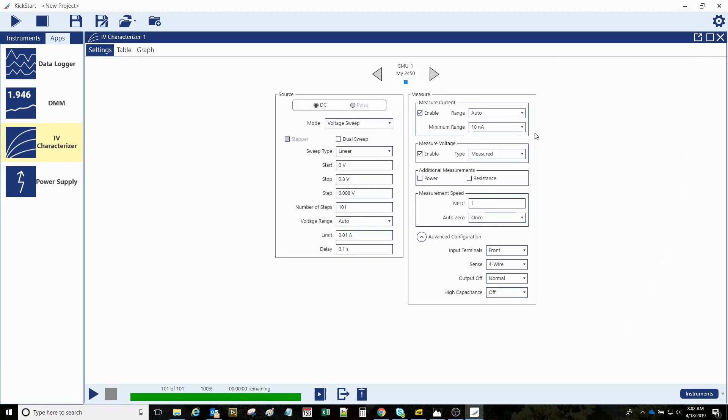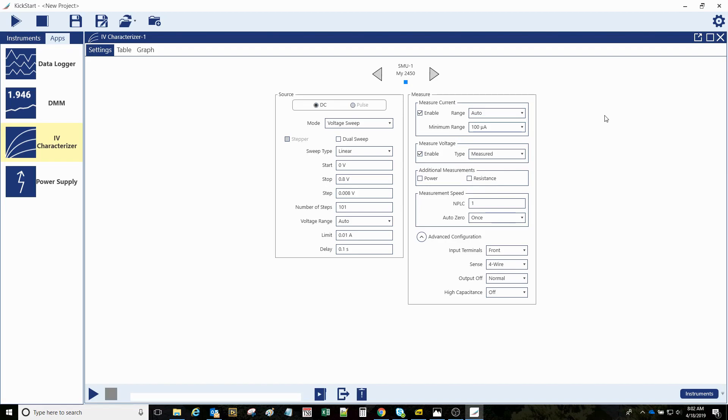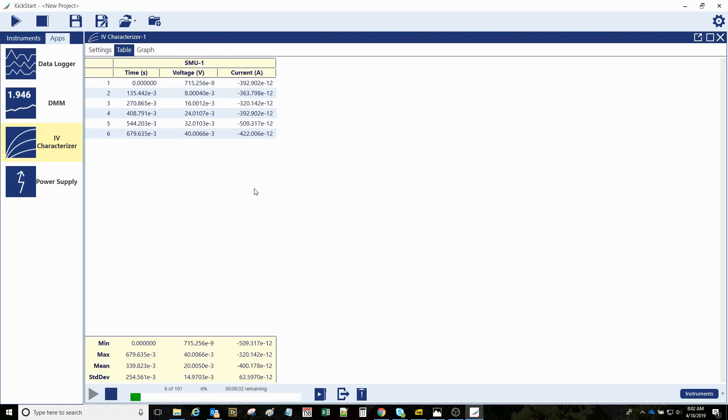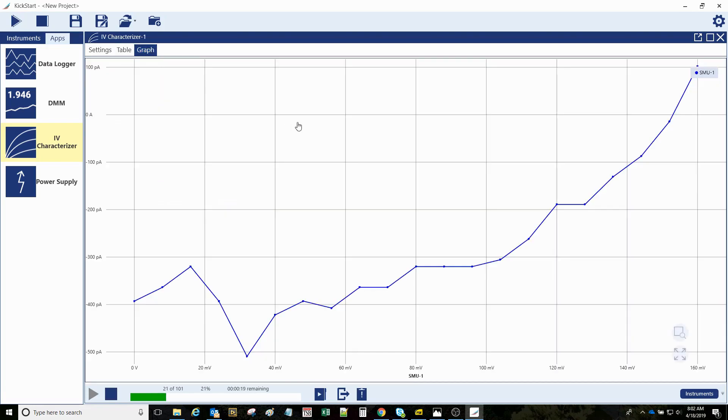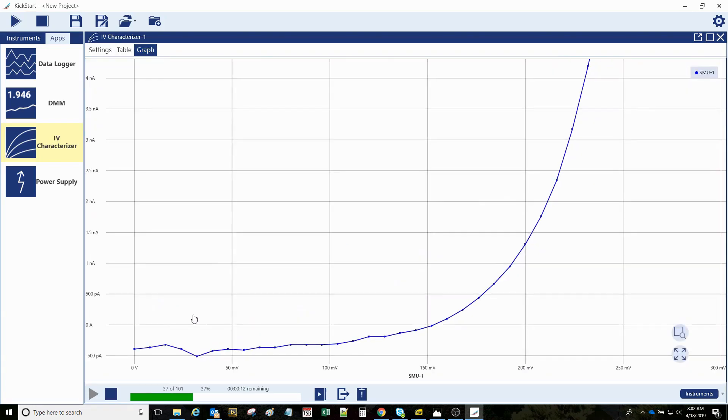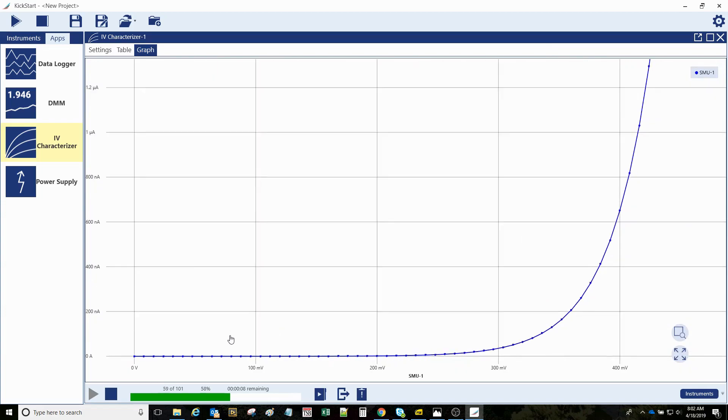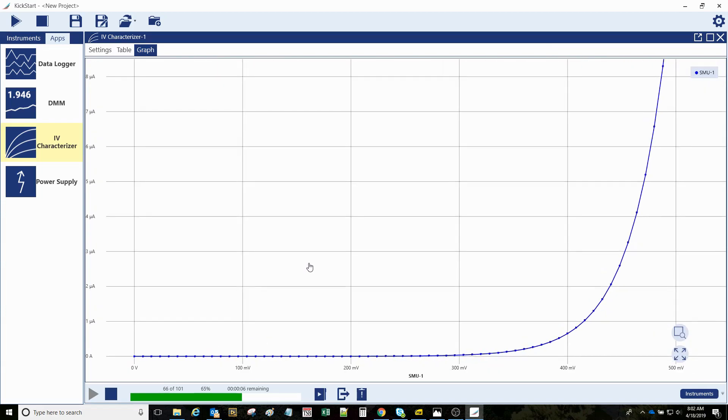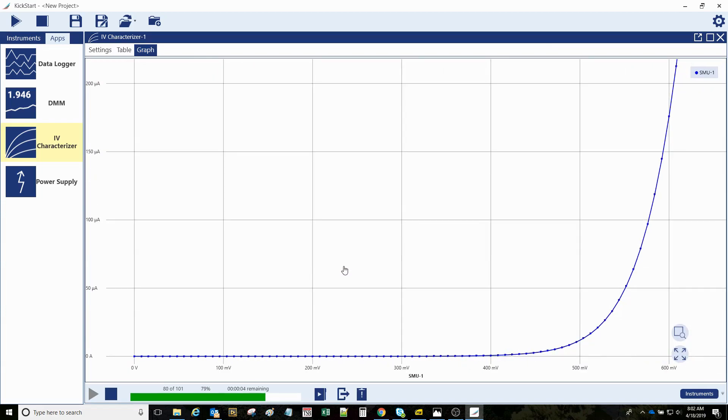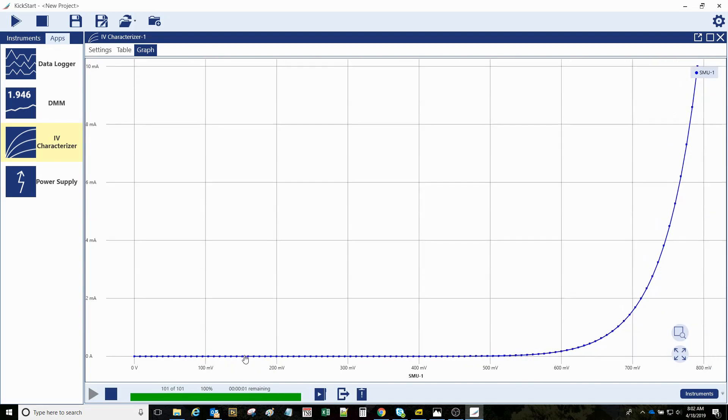So you can still assess those, but you could come into this measure range and set the minimum range that it's going to utilize for the test. Then it will still auto-range for that hundred microamps and higher, but the speed is much faster because these lowest and more sensitive, and therefore slowest, current measure ranges aren't utilized down here in the tiny numbers.